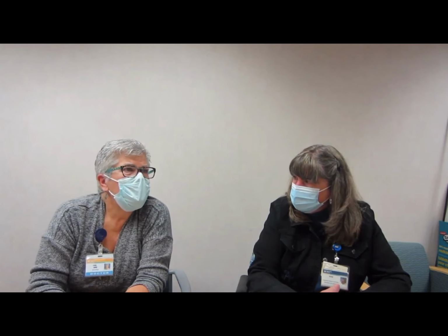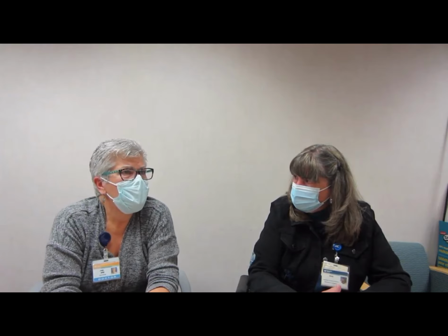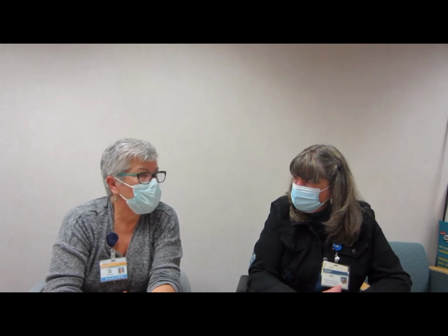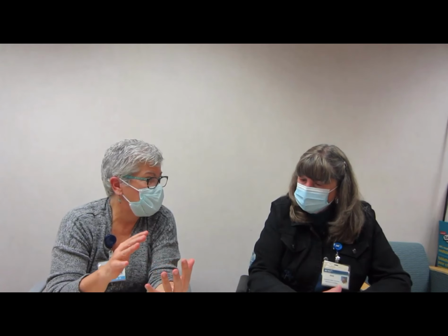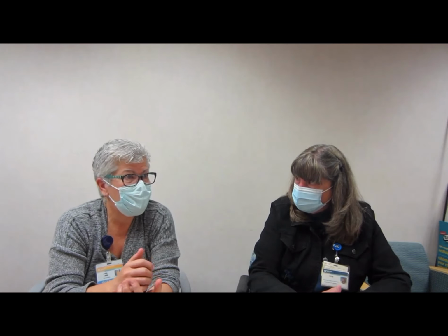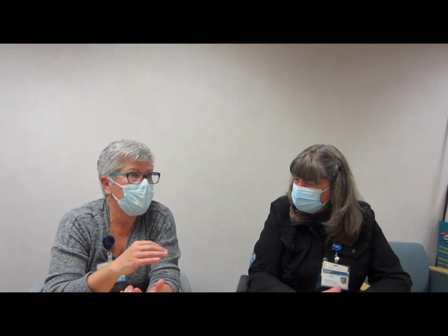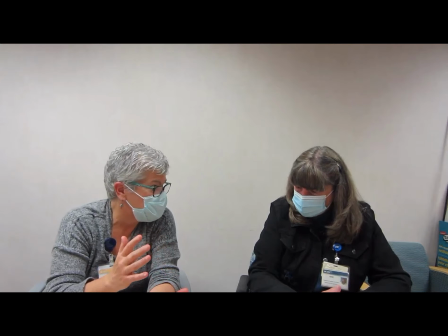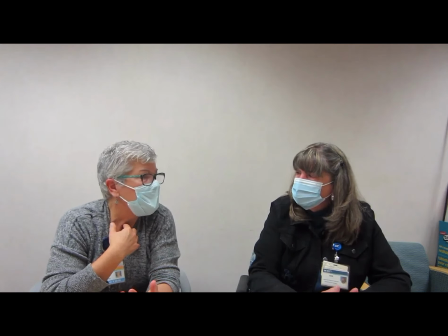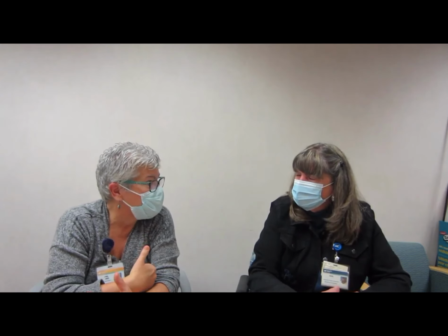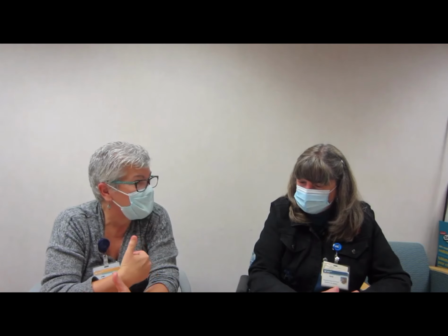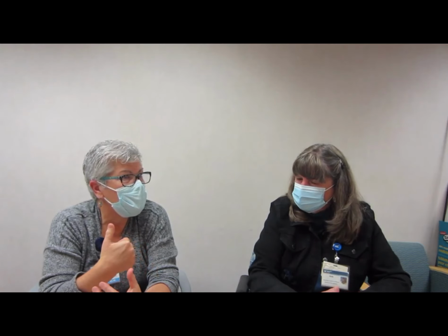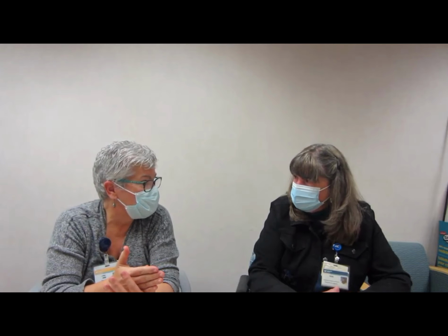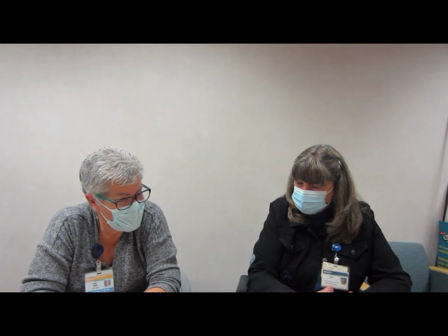So an increase in your servo pressure could be good because the baby's compliance could be getting better. Correct. It could be bad because there could now be a leak somewhere in your system, around the ET tube, or somewhere in the baby, like a pneumothorax. So it's the change that you're looking for. And if it's a dramatic change, then somebody needs to call respiratory or call the doctor to look at it.